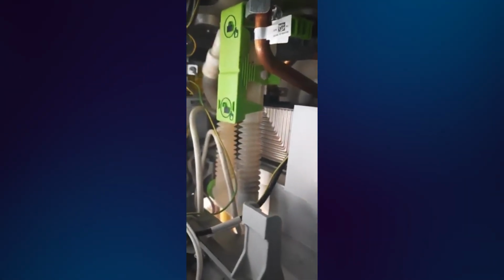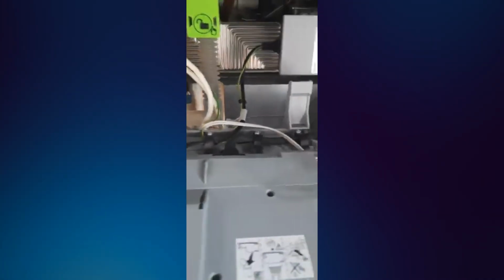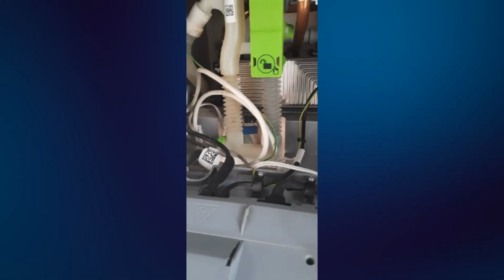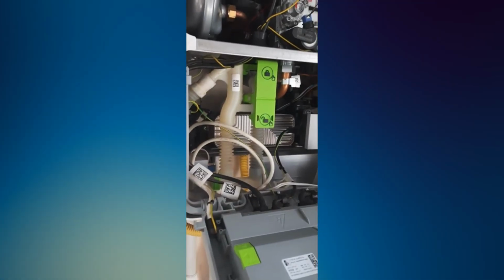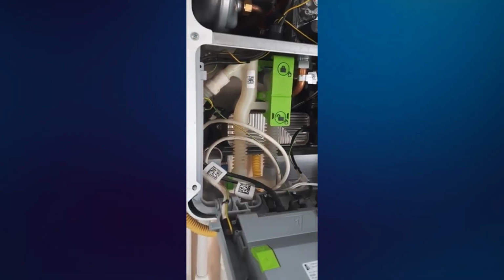The seventh possible cause is a dirty burner, blocked heat exchanger, or poor combustion condition. Over time, lack of servicing can allow dirt, debris, condensate residue, or combustion deposits to affect the burner and heat exchanger area. If the boiler cannot burn cleanly or transfer heat correctly, it may lock out. In some cases, users notice that the boiler heats more quickly after a proper service because the heat exchanger, burner area, condensate path, and sensors are working correctly again. But again, internal cleaning is not a normal DIY job. Burner pads, seals, electrodes, gaskets, fan connections, and combustion chamber components can be fragile and safety critical.